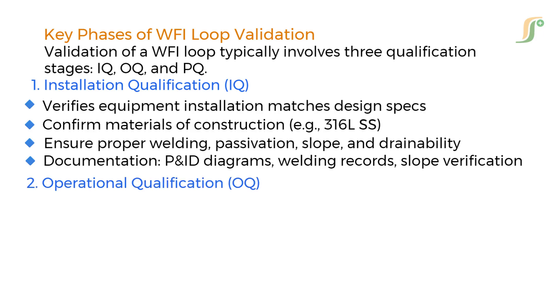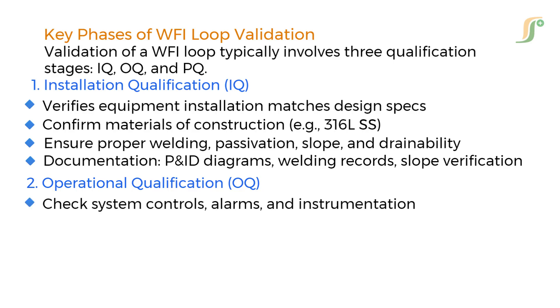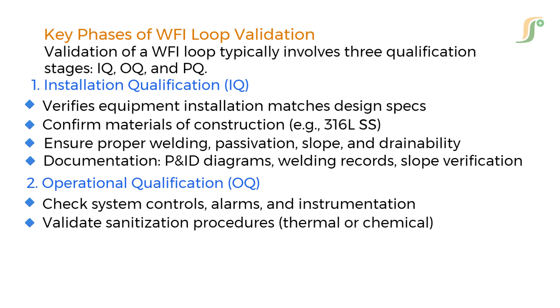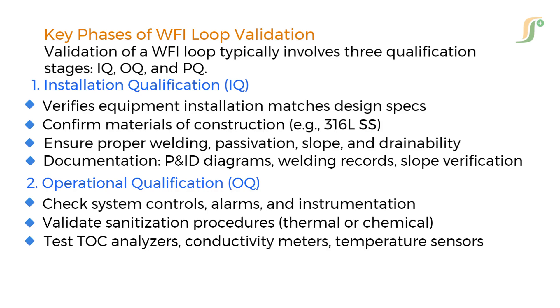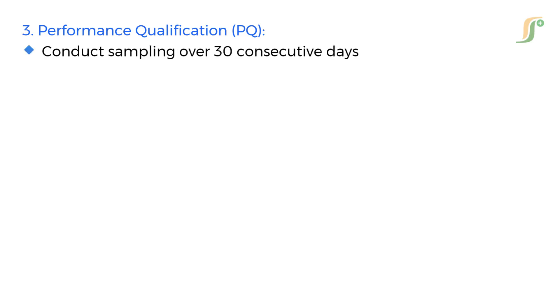Second, Operational Qualification: check system controls, alarms, and instrumentation. Validate sanitization procedures — thermal or chemical. Test TOC analyzers, conductivity meters, and temperature sensors. Verify recirculation rates and heat retention.